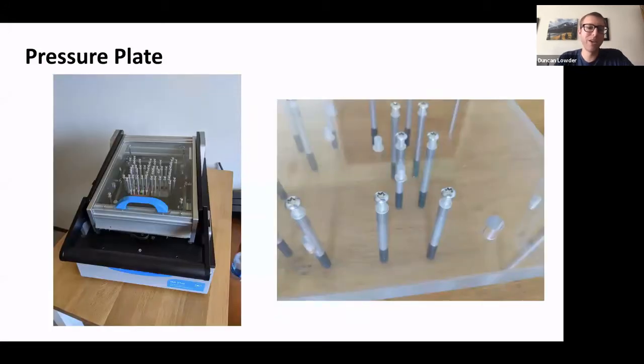The last part you need to customize on the test fixture is the pressure plate. This is the plate that actually pushes against the circuit board you're testing, and it pushes it against the test probes that are mounted into the probe plate.